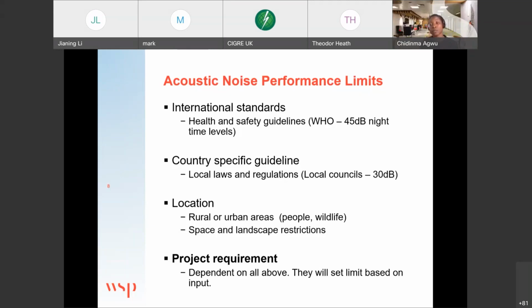That farm would be considered what you'd call a sensitive receptor. So the limit - basically at nighttime, that farm should, for example, not experience more than 30 dB. That's then setting your performance limit for how much noise your converter station can create, so that a certain distance away, where you have a sensitive receptor, it doesn't exceed that level.